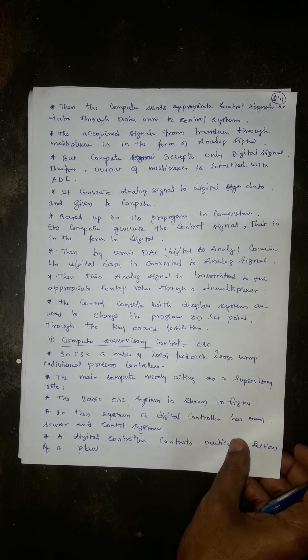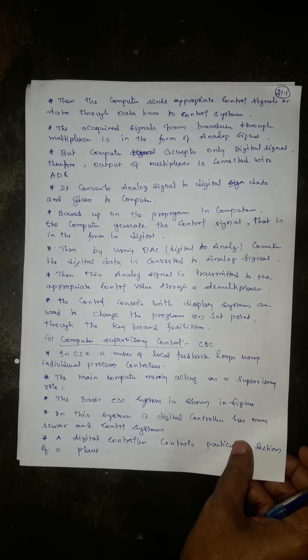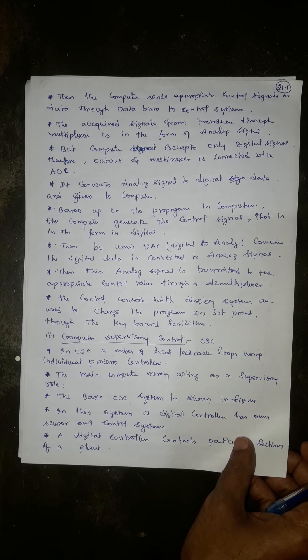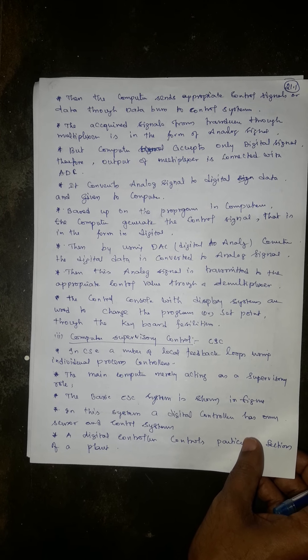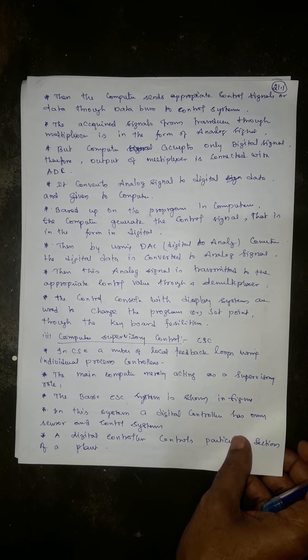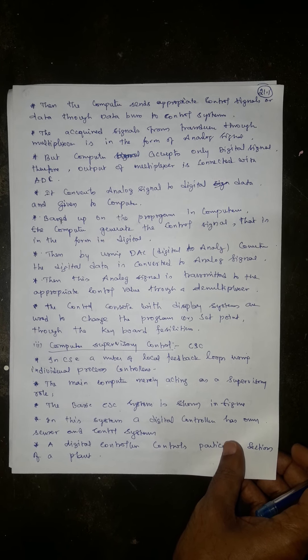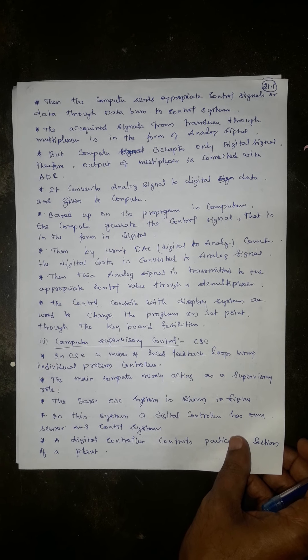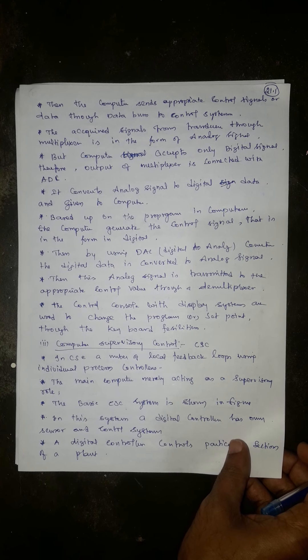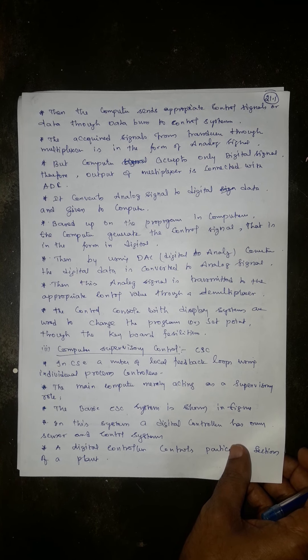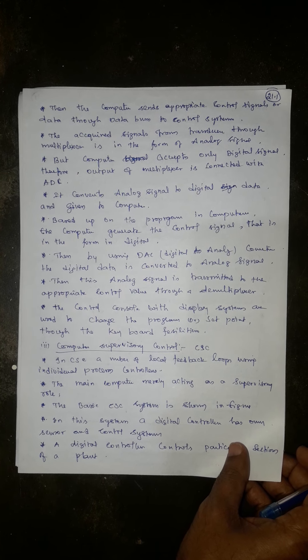Based on the program in the computer, the computer generates a control signal in digital form. Since the final control element, control valve, or control system is an analog device, a digital-to-analog converter (DAC) converts the digital data from the computer into an analog signal. This analog signal is then transmitted to the appropriate control valve through a demultiplexer.